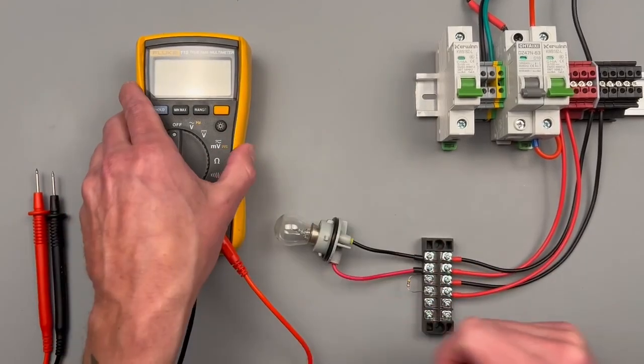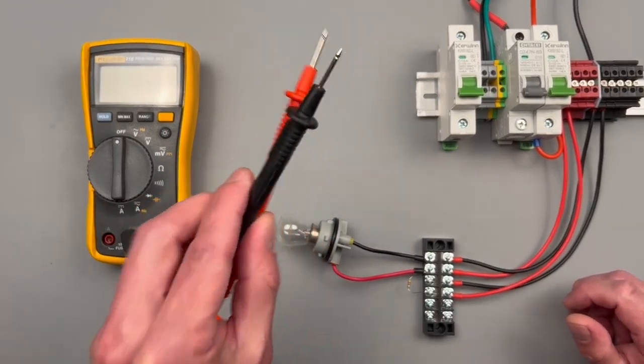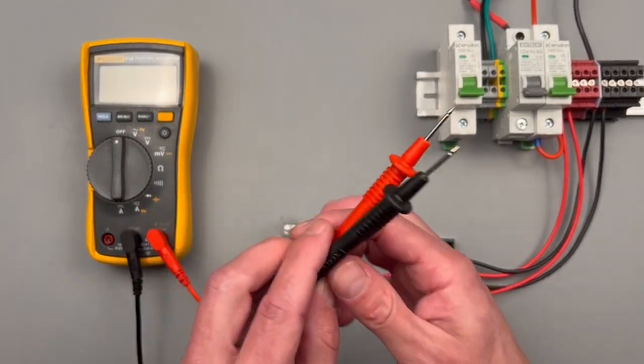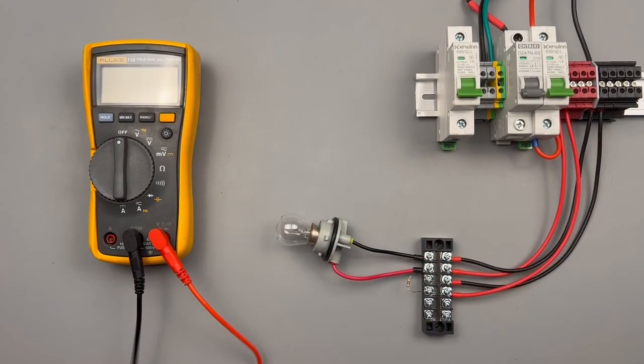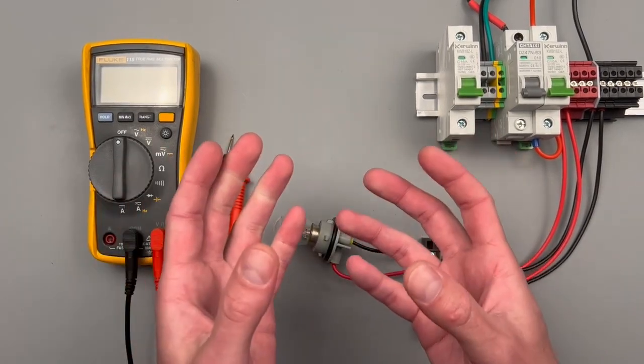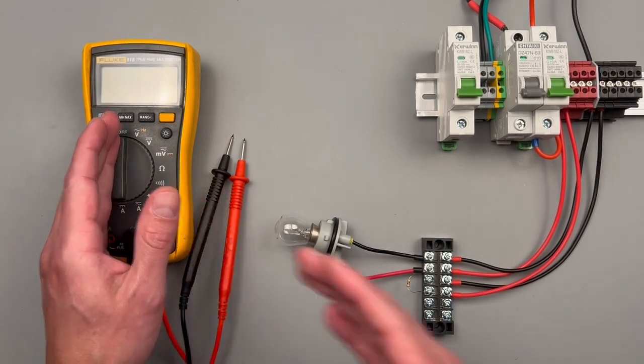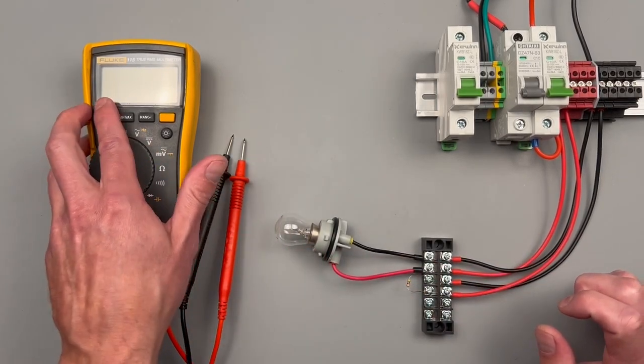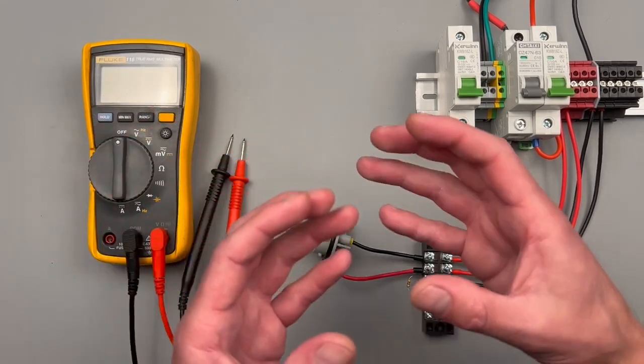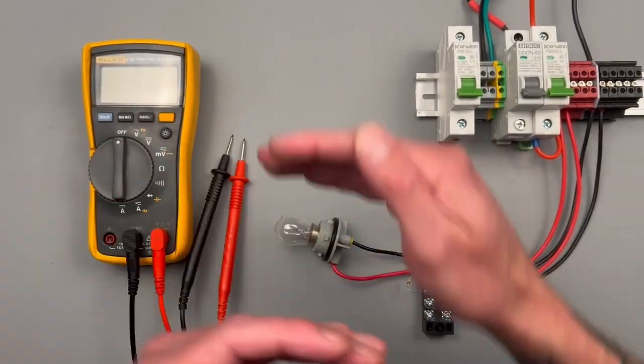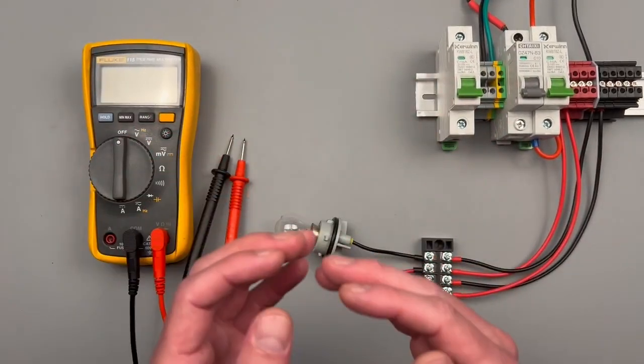Another thing that we need to keep in mind when we're measuring direct current is our lead polarity. That means your black and red lead, it's going to matter which one you use it for, or your measurement may not come back properly. It could tell your meter it's out of range, or the most likely case, it'll simply just have a negative sign displayed on the meter telling you that the polarity that you're using is reversed from what it should be, either because the circuit's been reversed or because your leads are reversed.